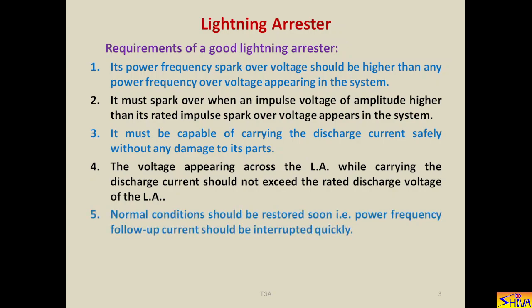And the last requirement from the lightning arrestor is that normal conditions should be restored soon. That is, the power frequency follow-up current should be interrupted quickly. Now when the lightning arrestor sparks over, discharge current is flowing, so there is a path of low impedance. So along with this impulsive discharge current, power frequency current is also flowing through this path of low impedance. This power frequency current is called the follow-up current. So as long as the discharge current is flowing, this power frequency follow-up current is also flowing.